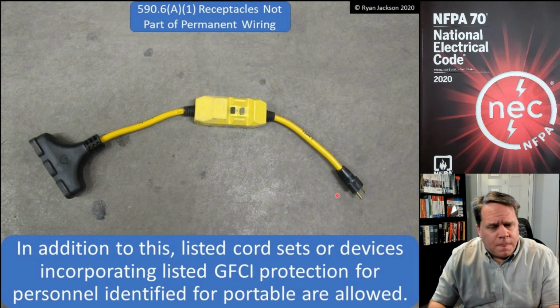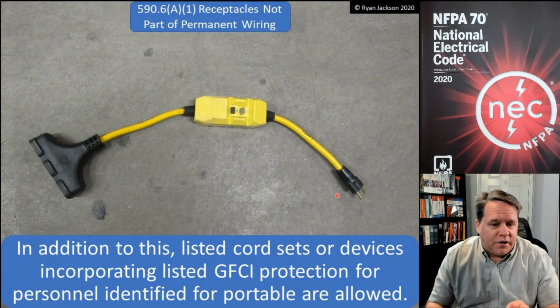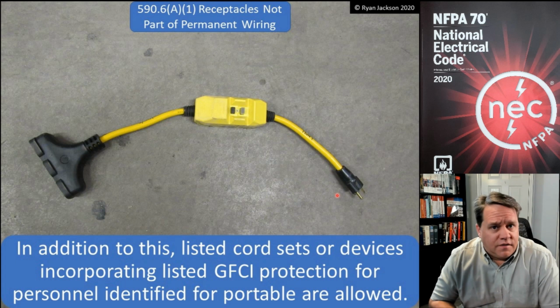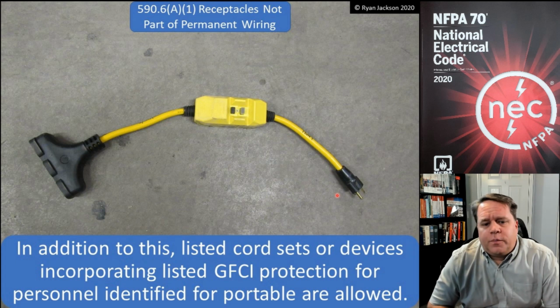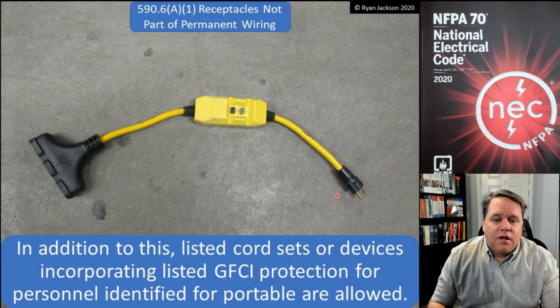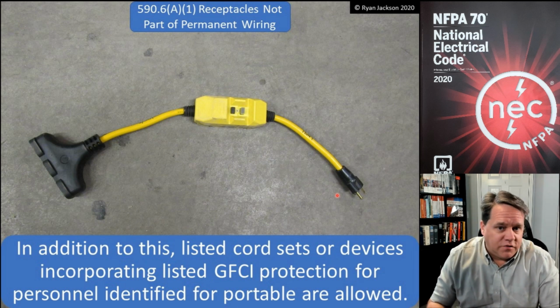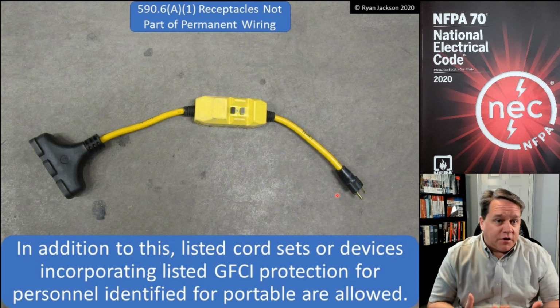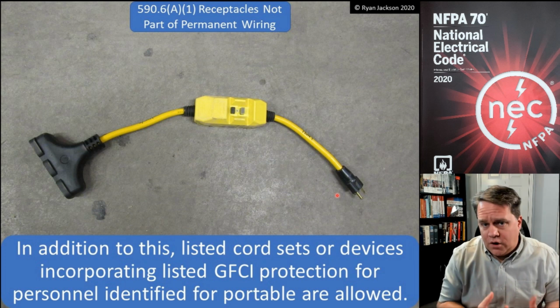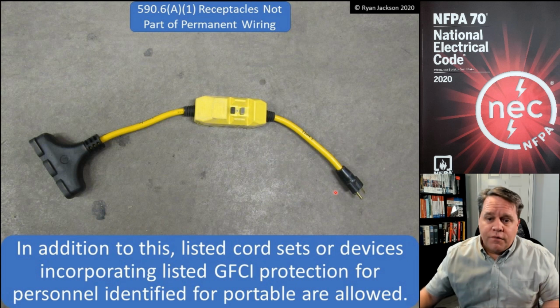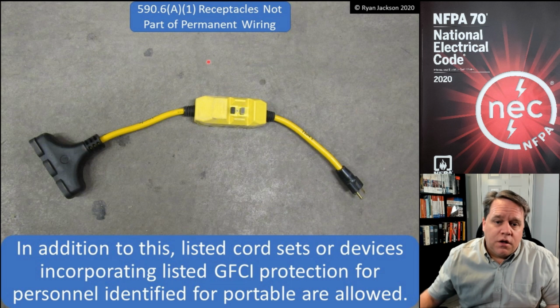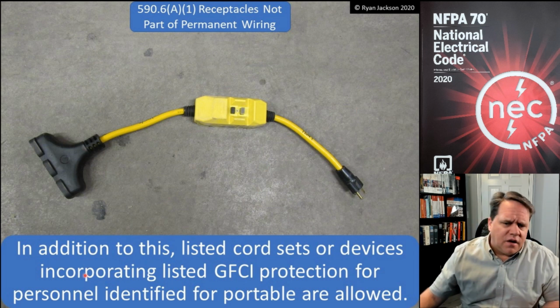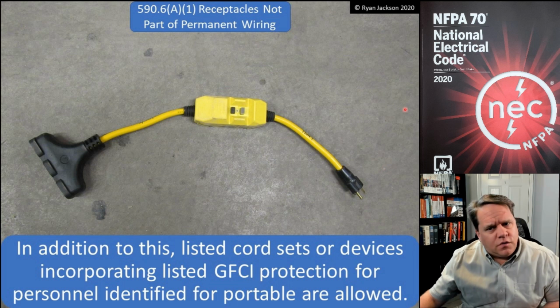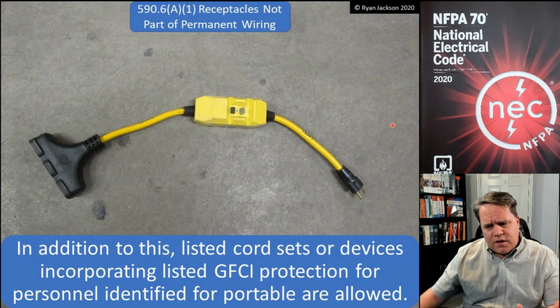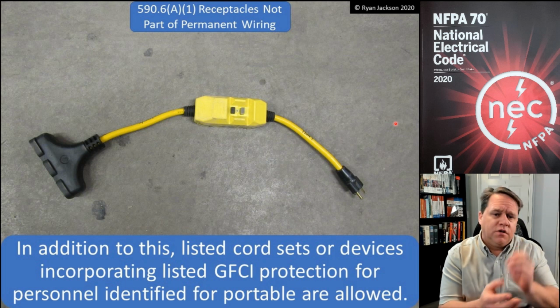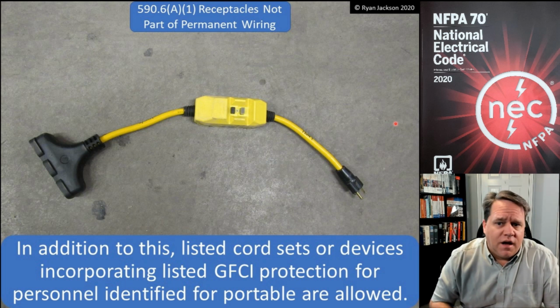If you keep reading, it also says that in addition to that protection, listed cord sets or devices that incorporate listed GFCI protection for personnel that are identified for portable use are allowed as well. All right, so we have to have GFCI protection for the receptacles that are not permanently part of the building. And if you would like, you can also add more GFCI protection in the form of these guys as well. It talks about being identified for portable use, and part of what that means is that it has open neutral protection. So if you lose the neutral, it will open the GFCI device.